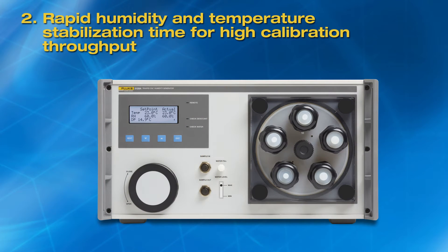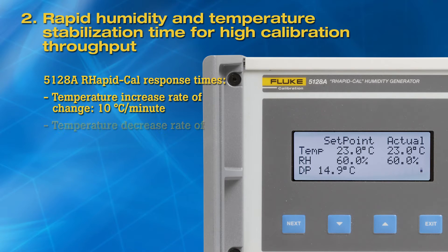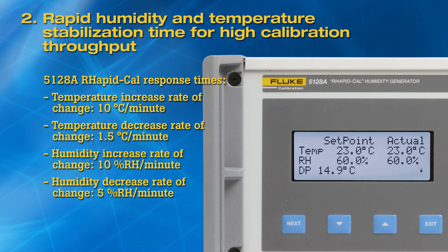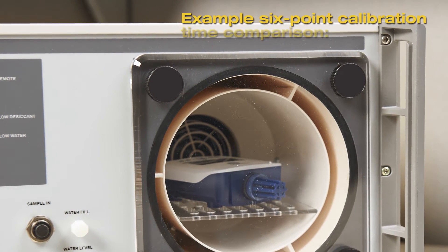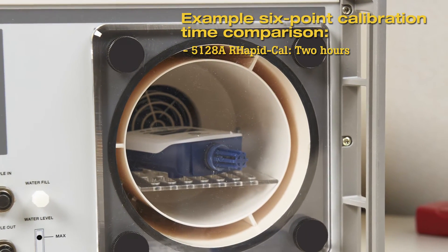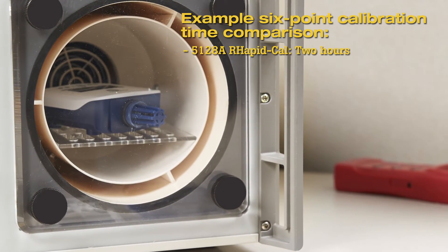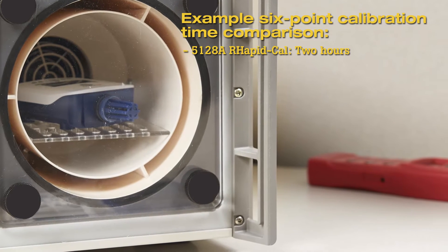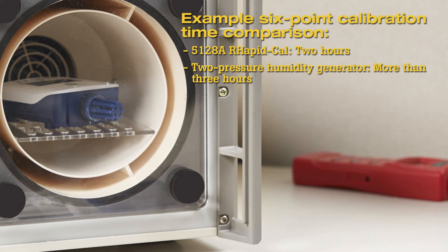Second, rapid humidity and temperature stabilization time for high calibration throughput. The materials and airflow design used in the 5128A RHapid-Cal are selected to ensure that response time to a humidity temperature step change is fast. A six-point calibration can be done in two hours using the 5128A RHapid-Cal. In contrast, a two-pressure humidity generator takes longer to respond to humidity or temperature changes. A similar six-point calibration with a typical two-pressure generator would take more than three hours.